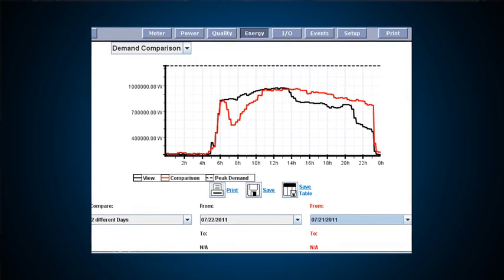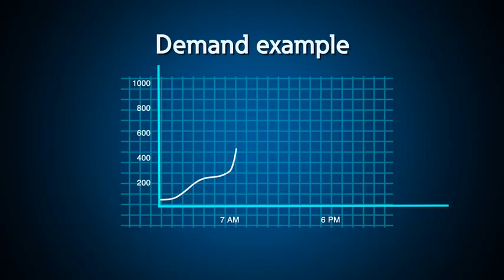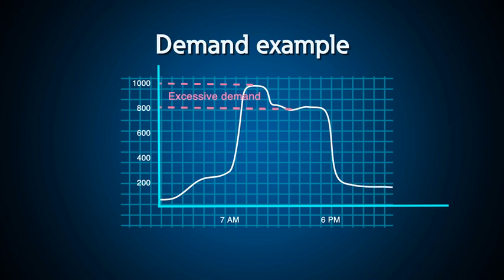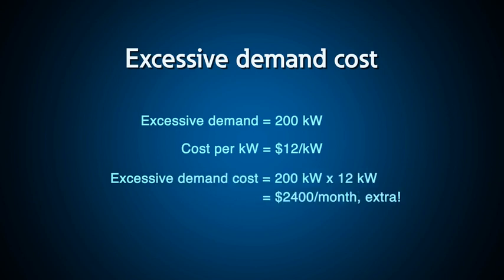The demand comparison is a great tool for facility owners and anyone who wants to understand patterns in your demand charges. For example, at one facility using this demand function, we determined that at about 7:30 a.m. the loads in a commercial building all came to life at about the same time, including lights, HVAC, and receptacle loads like computers. Because of this, there was a 200 kilowatt peak early in the day almost every day. At $12 a kilowatt demand, this meant that the customer paid about $2,400 a month in extra demand charges because of this peak demand, even if it only happened one time during the month.